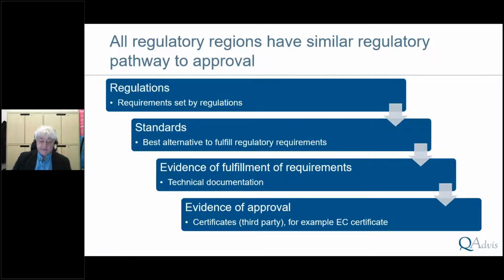All the regulations have a similar pathway. They are legally binding to follow. They also point out standards that should be complied with. The manufacturers must prove that they have satisfied the regulations in question by having proper documentation in place. And the regulators provide the manufacturers with evidence of approval, for example, a CE mark in the EU or a 510(k) clearance in the United States. If we take those two markets as an example, the expectations on documentation are similar, but to some extent different. A smart and cost-aware manufacturer generates the documentation needed without duplication of information.